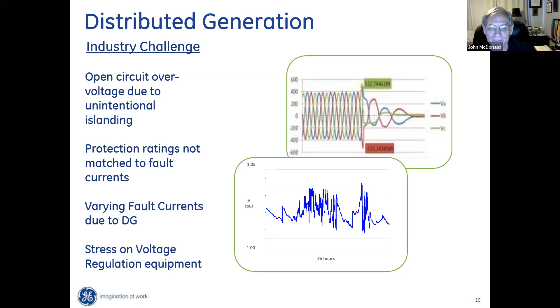But even more challenging is that load side contribution from distributed generation varies, varying fault currents due to distributed generation. Is the sun shining all the time? No. Is the wind blowing all the time? No. So the intermittency of the distributed generation causes the fault currents to vary. Very complicated situation, okay? And I'll talk more about voltage regulation equipment in a minute.